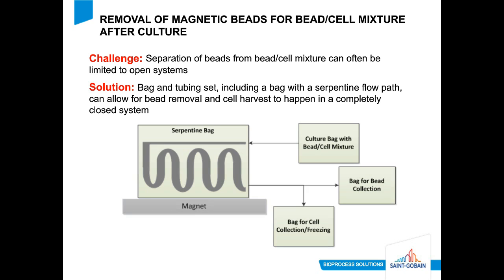So you'd have your culture bag with your beads and your cells in a mixture, and this is assuming that the beads have already been separated from the cells, but they still remain in the solution. And so typically you would run over a magnet. Now what we looked at is doing a very specific design that would allow for multiple passes over the magnet. So this is more of like a snake serpentine shape. And that would, between the flow and also the multiple passes, we saw that that offered really nice separation of the beads from the cells. So with the magnet on, you could flow the solution through and collect the cells directly for collection for the next step or even for freezing. And then you could turn the magnet off and actually collect the beads depending on if you were reusing them or just disposing of them.